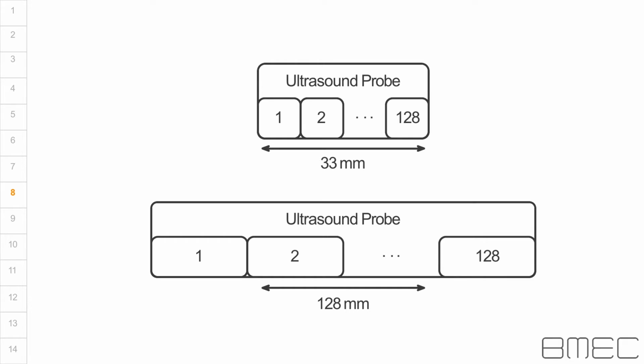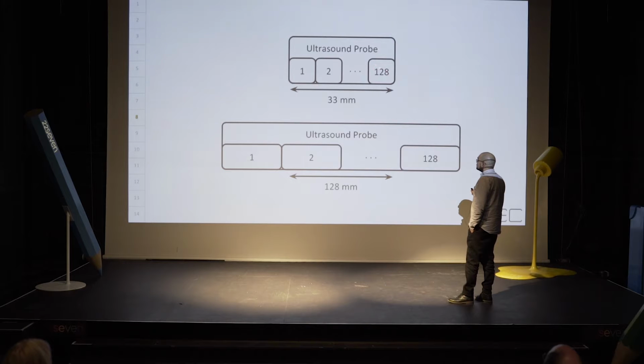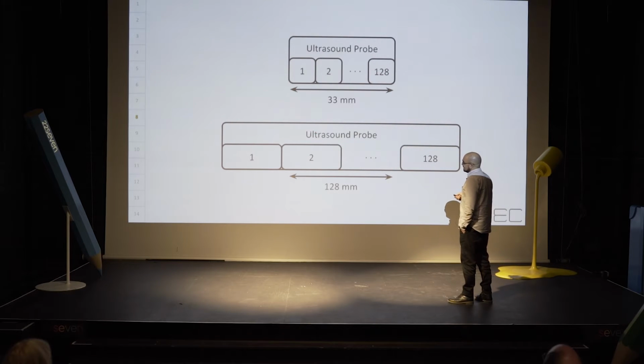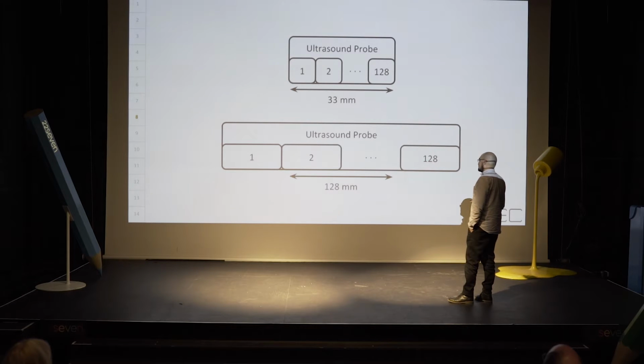Ultimately, we decided to put the multiplexer aside and consider our second approach of widening the acoustic elements. So this diagram illustrates that concept. Here's an ultrasound probe that has 128 acoustic elements of a certain length. There's another probe, also of 128 acoustic elements, and it's significantly longer, because the elements themselves have been widened. Widening the elements has pros and cons. The positive is that it increases the power of the probe, or the penetration depth that's possible. The negative is that as you widen the acoustic elements, the ultrasound image resolution drops.